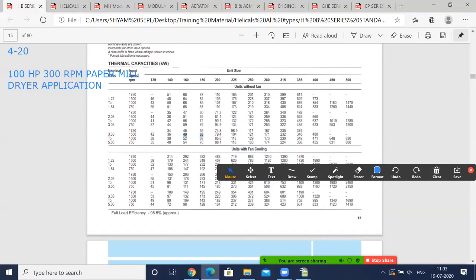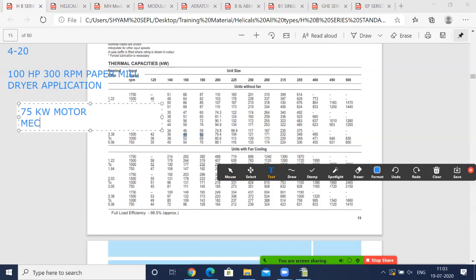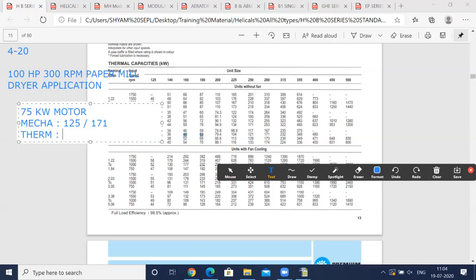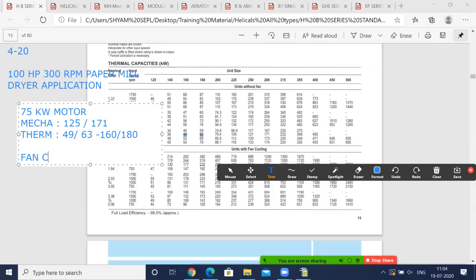As a thumb rule, the thermal rating should at least be 1.3 times the motor rating. So the motor is 75 kilowatt, and the mechanical capacity you have selected is 125 kilowatt or 171 kilowatt. You will offer both the options, but the thermal rating is 49 and 63 only. So model numbers 160 and 180 are not feasible without fan. Let's check with fan. With fan it is 109 and 143. That's a lot of improvement, you see. Fan cooling is very important in these bigger gearboxes, otherwise they will fail.